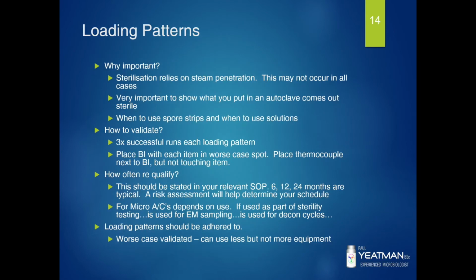Why is it important to actually validate loading patterns? Well, as I previously said, PIC/S PE 009-14 requires you to do validation. But it's also important to determine that you do get proper steam penetration, and that might not occur in all cases. So it's important to show what you put in the autoclave comes out sterile, and I discussed in the earlier slide when I've used spore strips and when I use solutions. So with validation, you want to validate 3 successful runs for each loading pattern, which shows reproducibility. You'd place the biological indicators next to your worst case spots and place a thermocouple also next to the biological indicator but not touching, just so you can show that the BI got to the right temperature over the right amount of time.